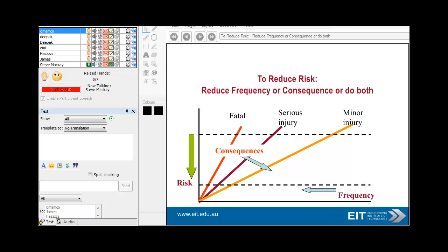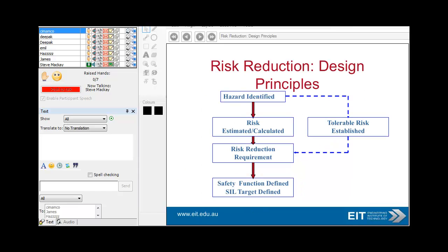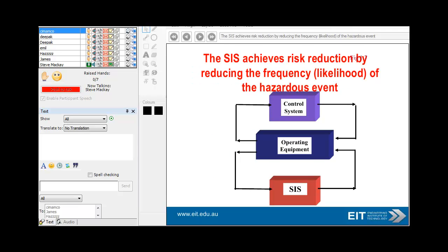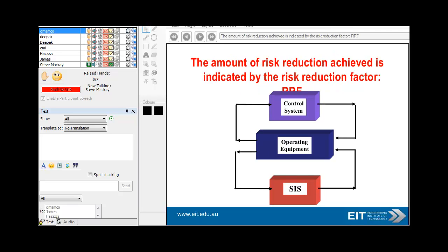To reduce risk, reduce the frequency or consequence — or ideally both — making events as unlikely as possible. The risk reduction design principles are: identify the hazard, work out the risk, estimate or calculate it, look at the risk reduction requirements, then establish the tolerable risk and define the safety function. Safety control systems must operate independently of the process control system, so that if the control system has a problem, it does not impact plant safety.